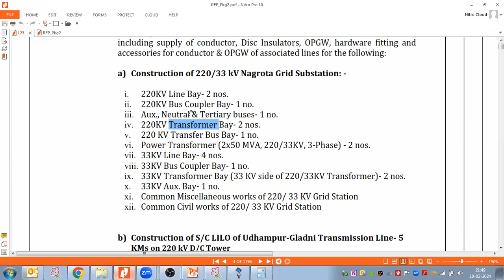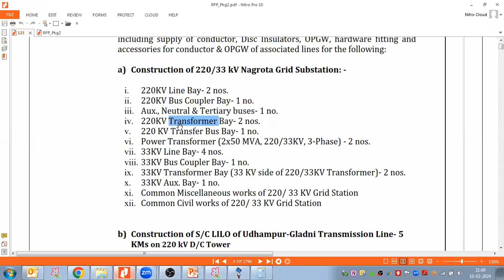Okay. Now, another thing: if you compare this scope of the work and this scope of the work, in this particular scope of the work, I'm using the reactor. But in this scope of the work, there is no reactor. Only, as you see here, line and then transformer bay, transfer bus, power transformer, 33 kV line bay. But here I'm using the reactor. So let us understand where we use a reactor, where we don't use a reactor, and why we use the reactor in extra high voltage substations.